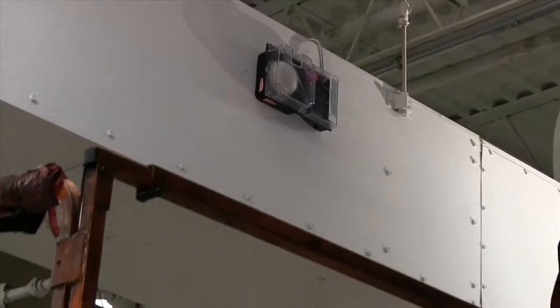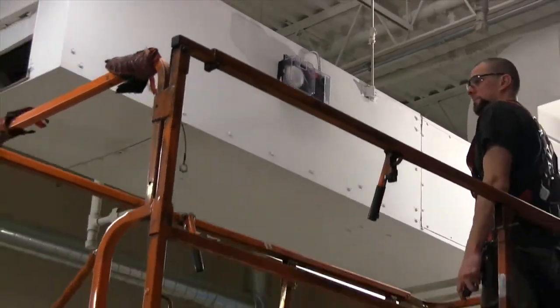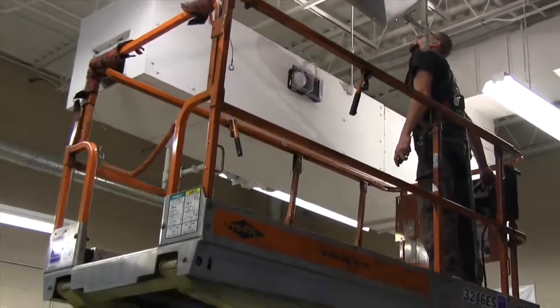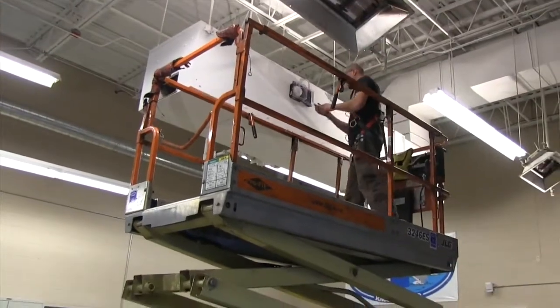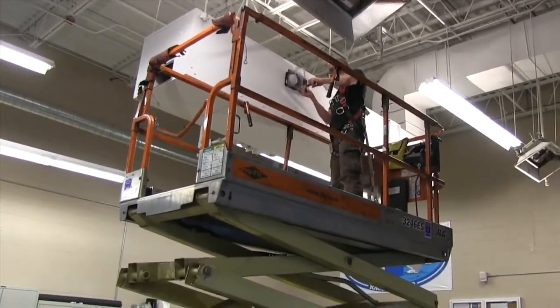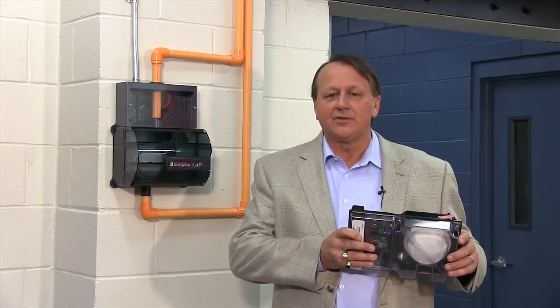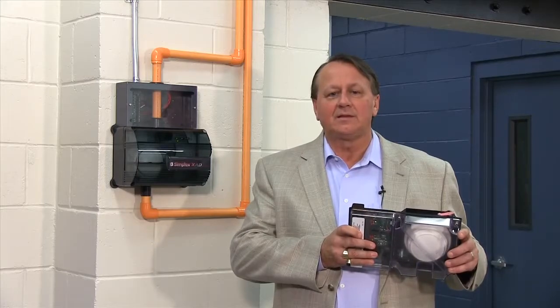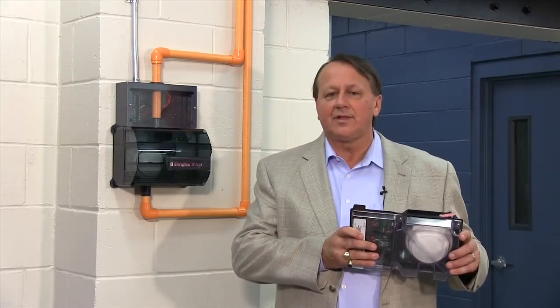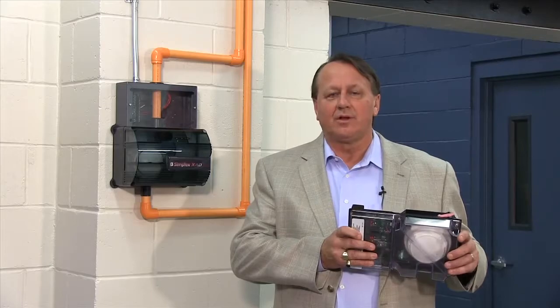In fact, it is not uncommon to find a duct detector mounted in a location where it can only be accessed for testing or service by using a lift. This is expensive and can discourage testing or maintaining duct detectors. Over time, this lack of service could result in nuisance alarms.